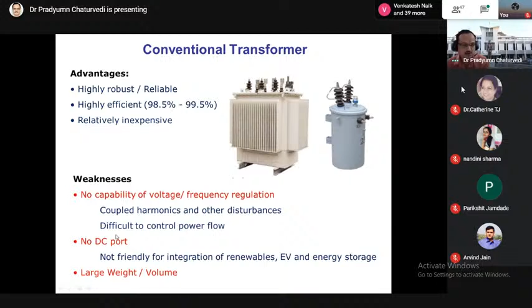Now what it will do and what duties it has to perform. In this traditional MVAC bus, we need communication based on IEC standard and some other standards for smart communication. And second, this SST will give you the flexibility of achieving or implementing a low voltage DC bus separately and a low voltage AC bus separately.